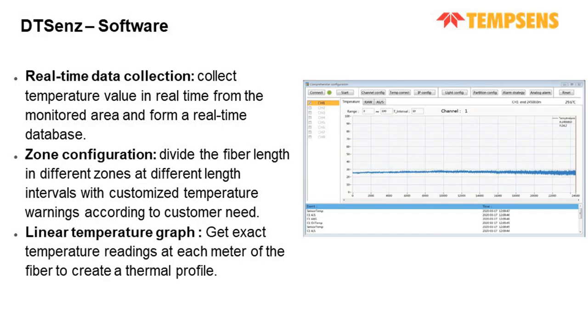The system architecture supports customizable zone configuration, allowing the fiber to be segmented into discrete monitoring zones. So we can divide the fiber into multiple zones depending upon the area where it is installed. These zones can be defined based on application specific requirements, such as critical infrastructure points. We can divide it into environmental segments, or as per the asset location, different assets, with user-defined temperature thresholds. Each zone can have its own temperature threshold. Some can have the alarm at 100 degrees centigrade, some zones at 80 degrees, and like that. This zoning capability provides granular control over alert generation and enhances the system's ability to localize and respond to thermal anomalies.